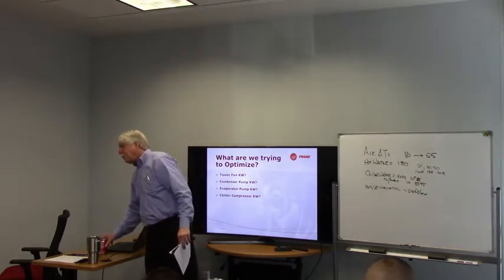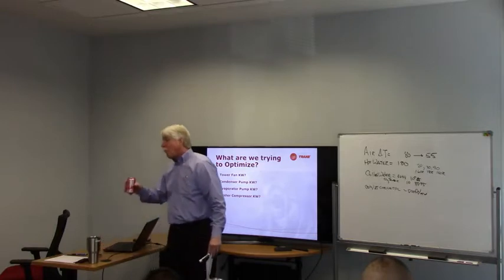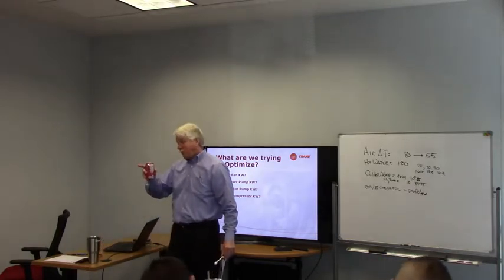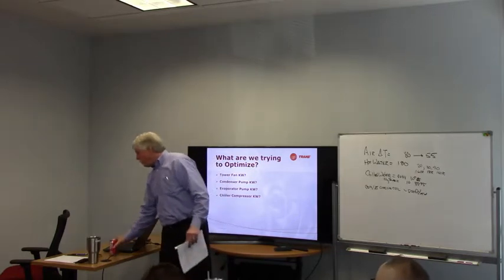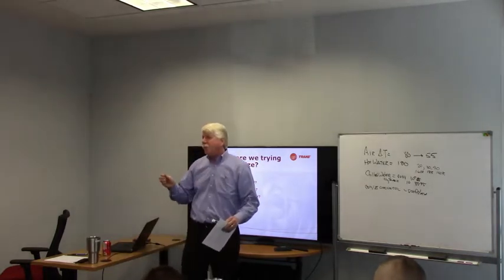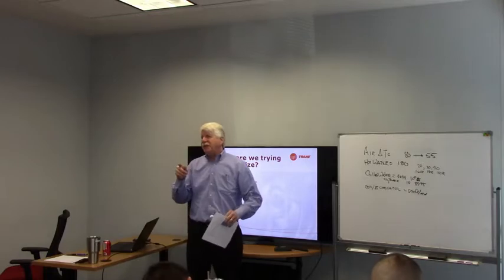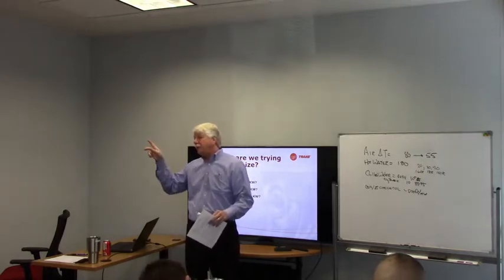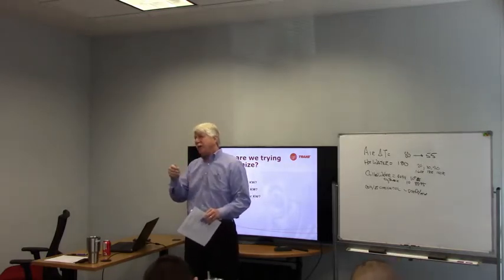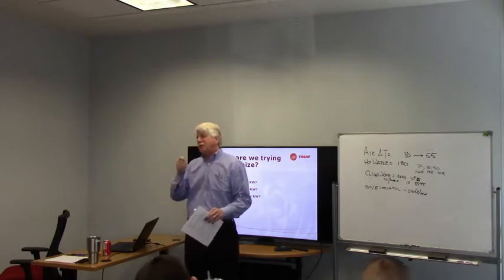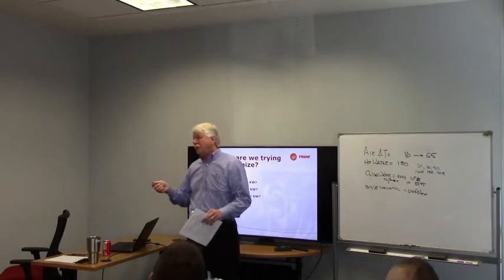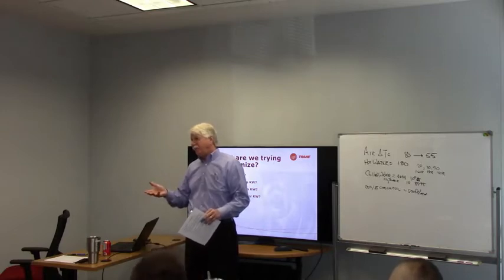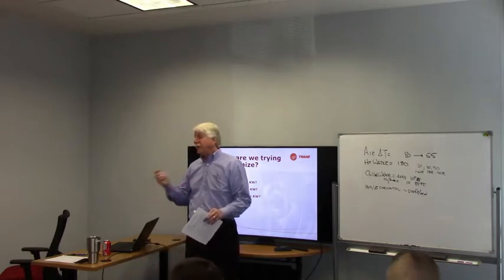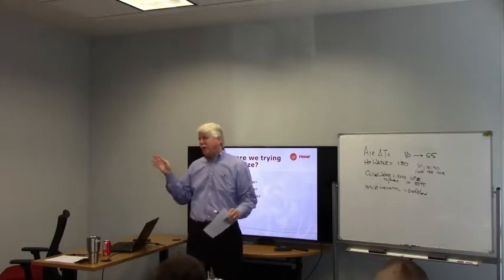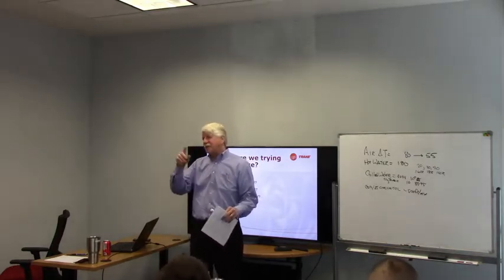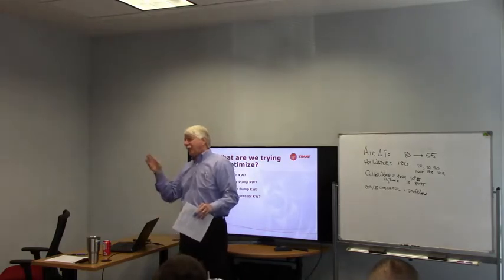It goes by basically 12, like the tonnage, or like the BTUs, right? So like multiples of 12, 12, 24. Yeah. The important thing is those are MBH. So like if you see a YCD and it says 06, or it says 600 on it, that doesn't mean it's a 60 ton. It means it's 600,000 BTUs, which means it's a 50 ton. Okay? Once you move to IntelliPaks are all tonnage. So like if you see an SFHA 50, that means it's a 50 ton.